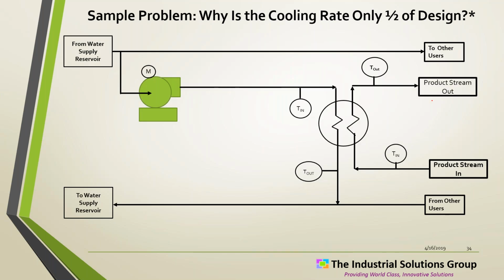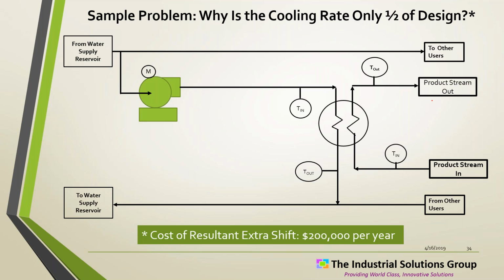So I want to give you a sample problem, and we're going to go through it pretty quickly, but this is a real problem from our files. It's going back 15 years or so. I had a client call and say, I've got a problem, Mike. I've got this process heat exchanger, and I can't get enough cooling. I'm supposed to be making 200 pounds per hour of product, and I'm only making 100 pounds per hour. It's half the design rate. And it's costing me $200,000 per year, because at design rates I should be able to get everything done in one shift. It's forced me into a second shift, and I can't figure it out.